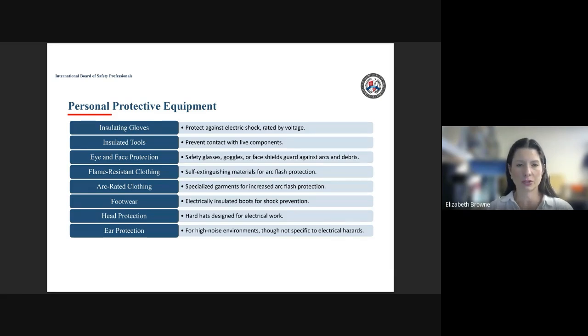But anybody working with live electrical equipment should at minimum be wearing insulated gloves that are rated for the voltage they're working with, and insulated tools. The tools are especially important to be insulated because tools are typically made of metal, and metal is a conductor of electricity. Additionally, eye and face protection such as safety glasses, goggles, and face shields should be used. Flame resistant clothing or arc-rated clothing may be required. Electrically insulated boots or footwear is another level of protection for qualified electrical workers or those individuals that will be working with live electricity.